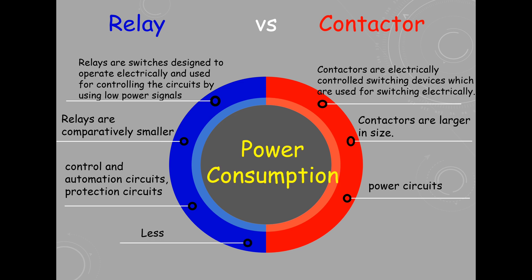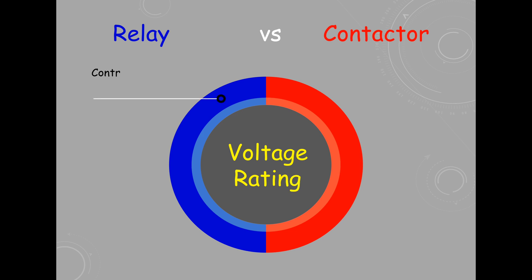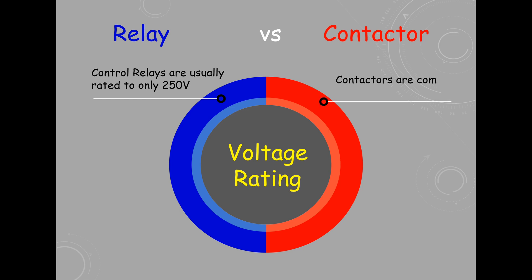The power consumption of a relay in circuits is very less, while the power consumption of a contactor is comparatively more. Relays are usually rated to 250V only, whereas contactors are commonly rated for up to 1000V.